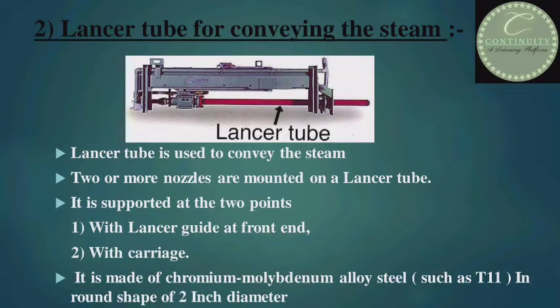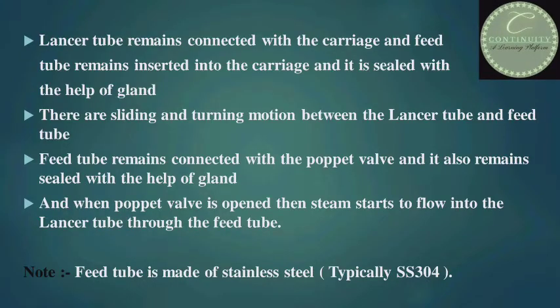Second part: lancer tube for conveying the steam. Lancer tube is used to convey the steam; two or more nozzles are mounted on a lancer tube. It is supported at two points — first, at the front end with a lancer guide, and second, with the carriage. It is made of chromium-molybdenum alloy steel, such as T11, in a round shape of 2-inch diameter. The lancer tube remains connected with the carriage, and the feed tube remains inserted into the carriage till the front end and is sealed with the help of a gland. There is sliding and turning motion between the lancer tube and feed tube. The other side of the feed tube remains connected with the poppet valve and is also sealed with a gland. When the poppet valve is opened, steam starts to flow into the lancer tube through the feed tube. Feed tube is made of stainless steel, typically SS304.